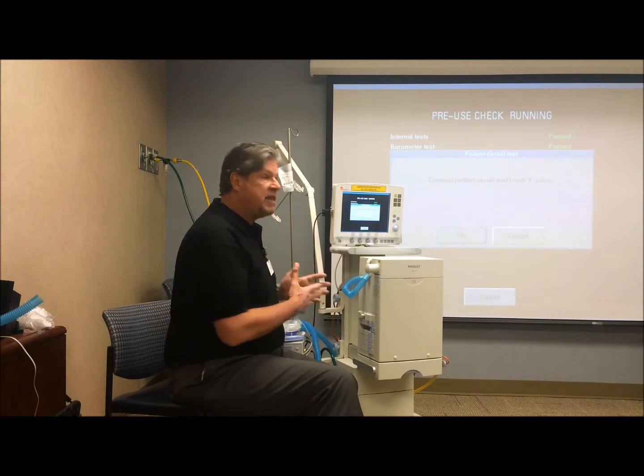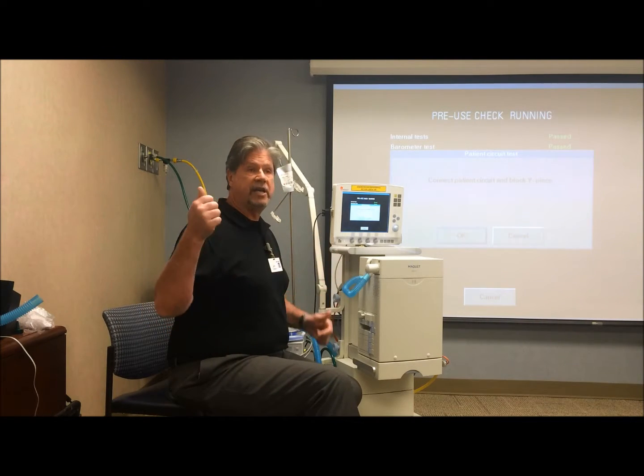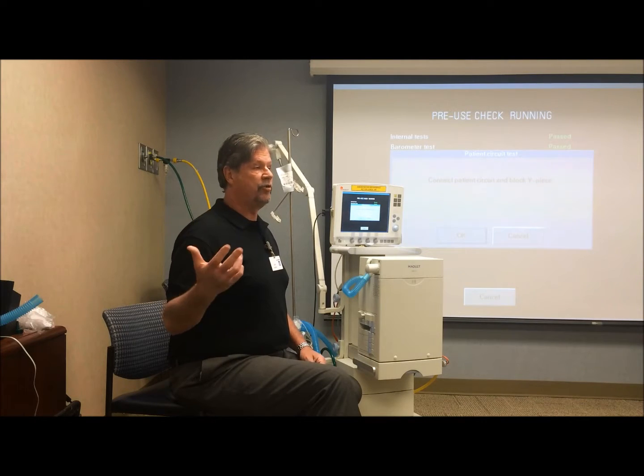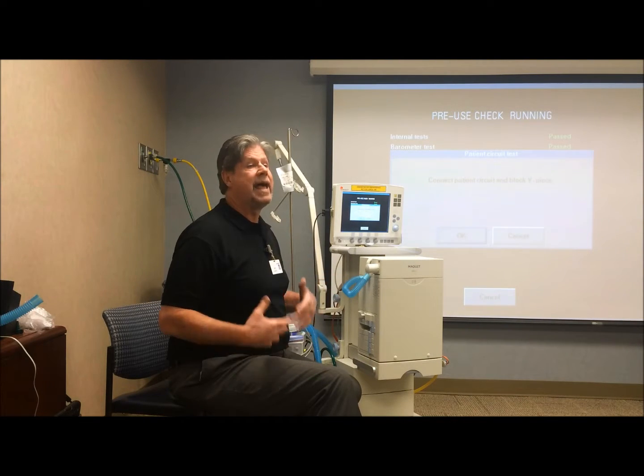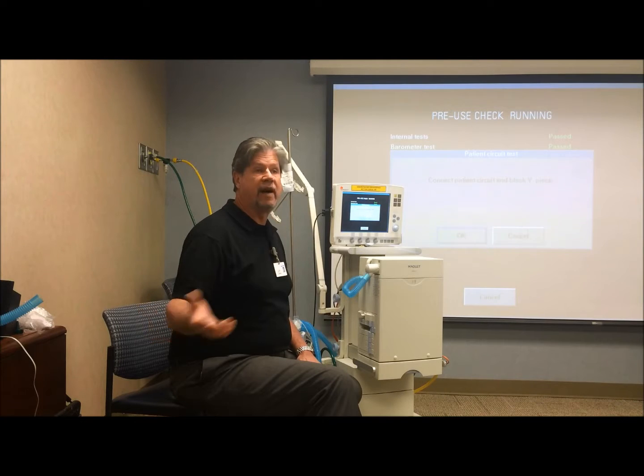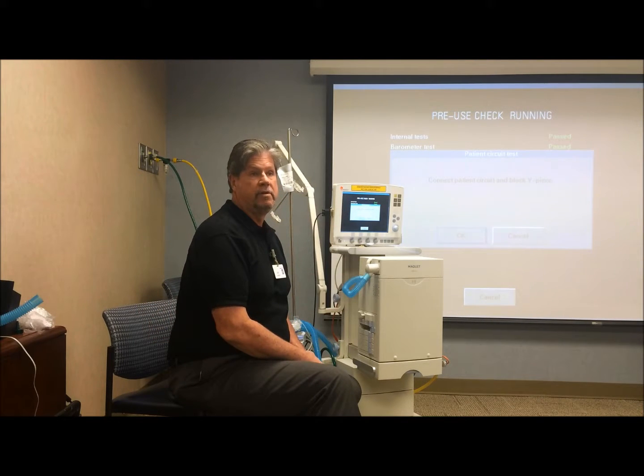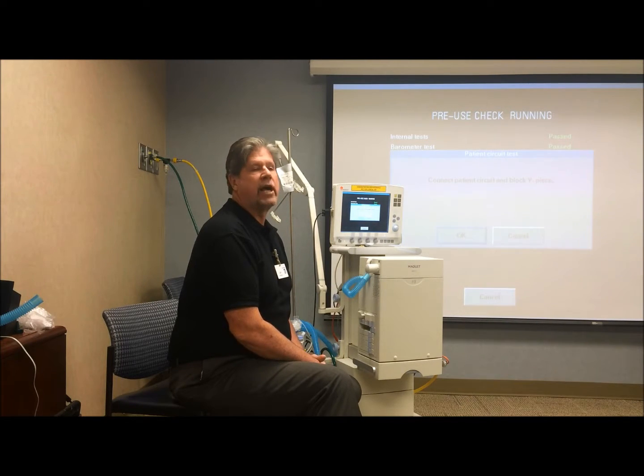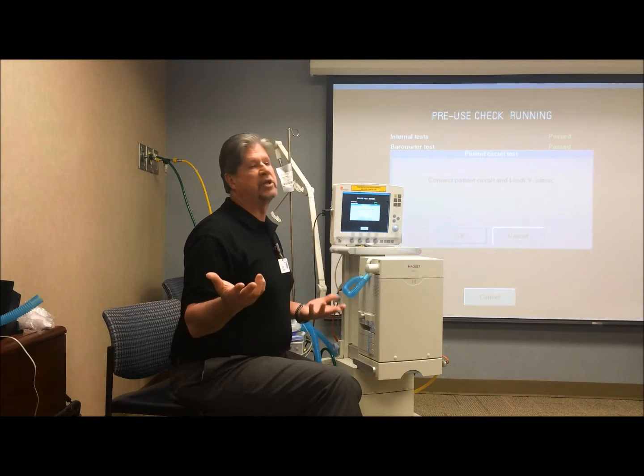So if in the MR suite you simply do a circuit test, the ventilator will know how much it loses for that circuit, and it will compensate, so you're always delivering 500, and you don't have to bump it up. Well, it's easy just to do an extra 25, 50. Just bump it up. You don't have time to really calibrate that. Okay, all right. But just so you know the principle, right?